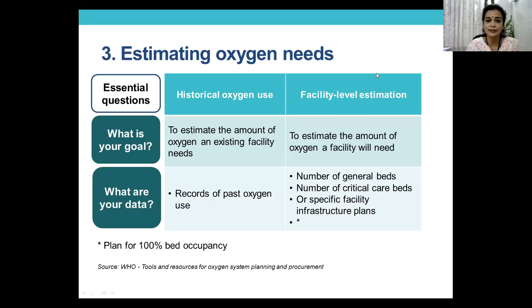This is a WHO way of calculating the peak load. They say that if you have 700 standard general beds, you may not have points for all 700 beds. You may only keep, probably, 1 oxygen point for 6 beds. But while you are calculating, you will calculate for all the beds at the rate of 0.75 liters per minute. It's not that you are going to give 0.75. You may give the patient 4 liters. But while you're calculating for 700 beds, 0.75 liters per minute is what you calculate.